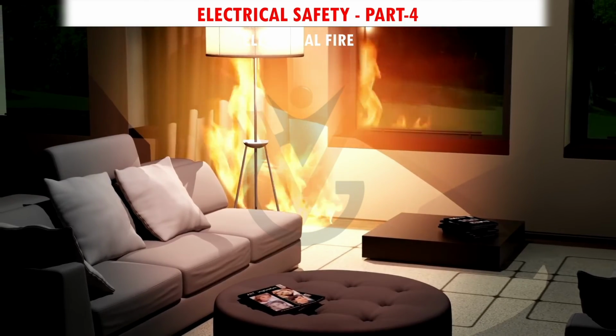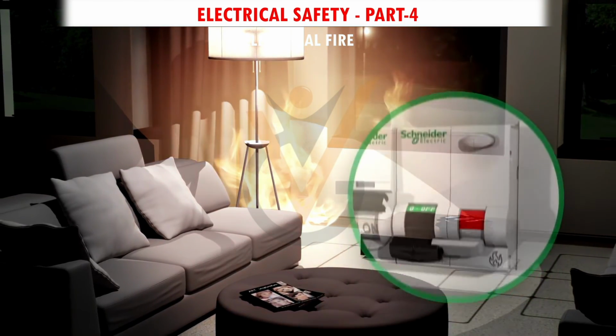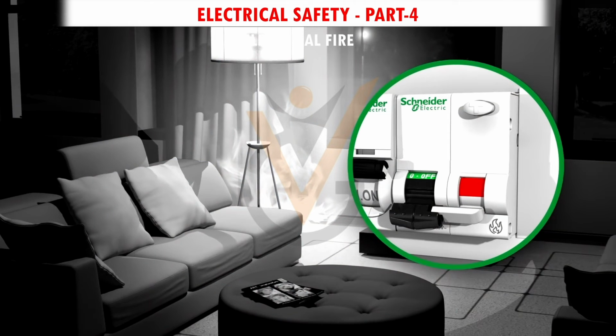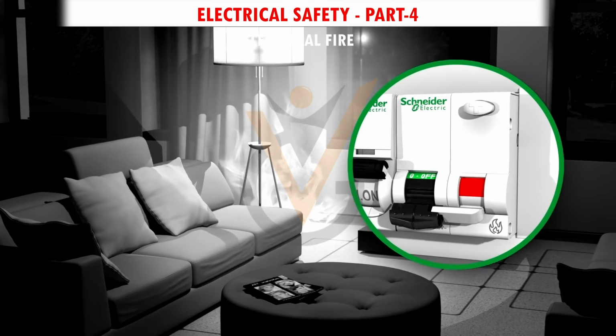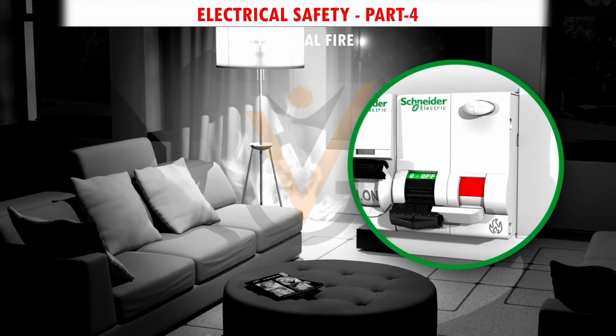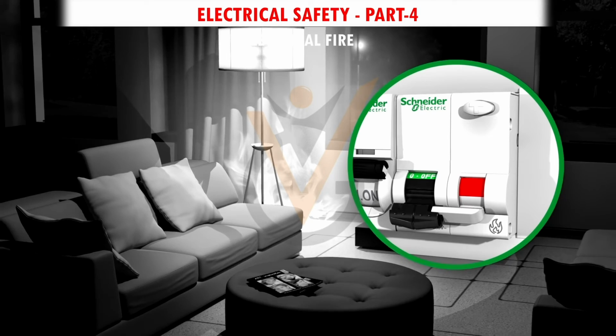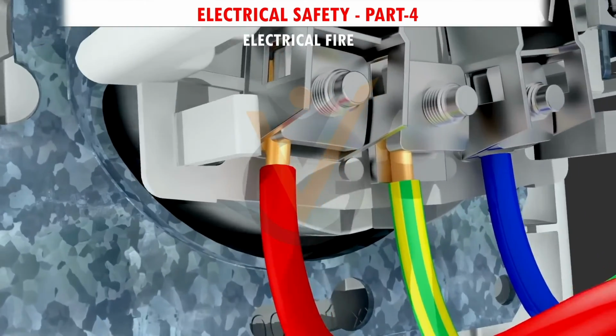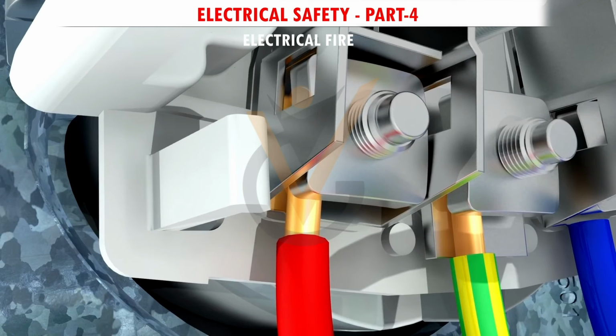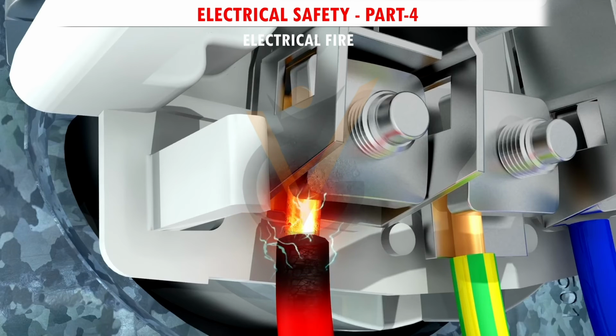Now you can protect against this kind of fire with the arc detector. You can stop the vicious circle before it takes hold. To understand how the detector works, let's walk back through our scenario. The connection pulls apart, overheats, burns the insulation and socket, which produces carbon. The carbon acts as a conductor and carries some of the current, generating electric arcs.